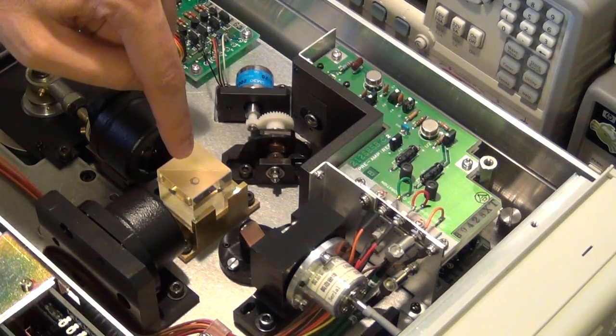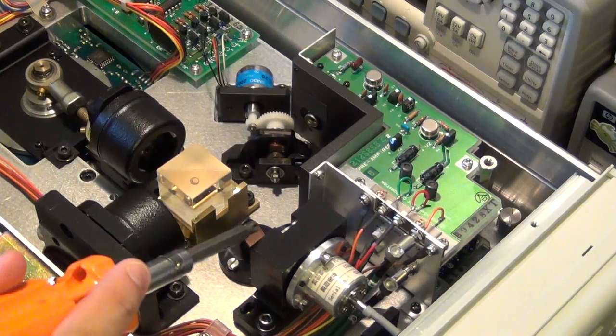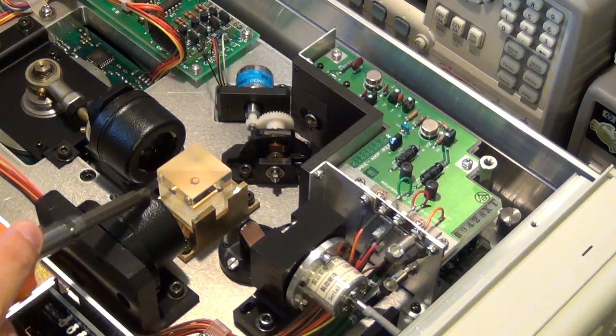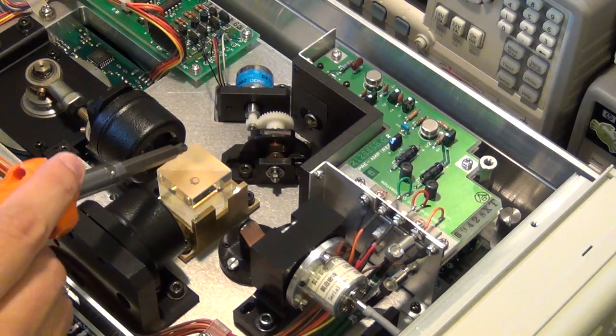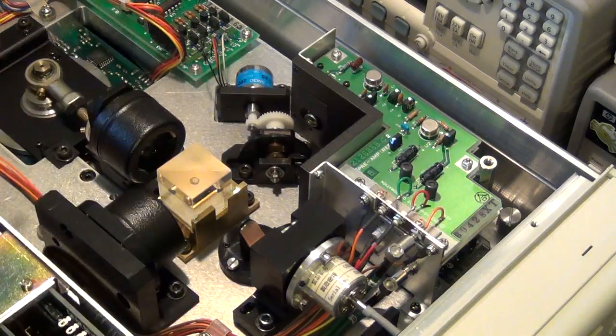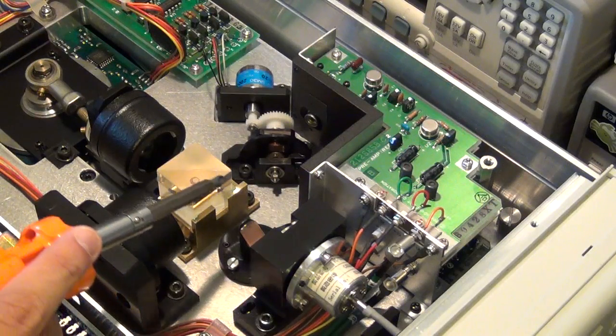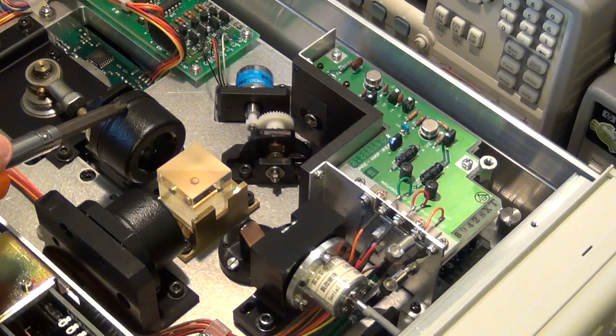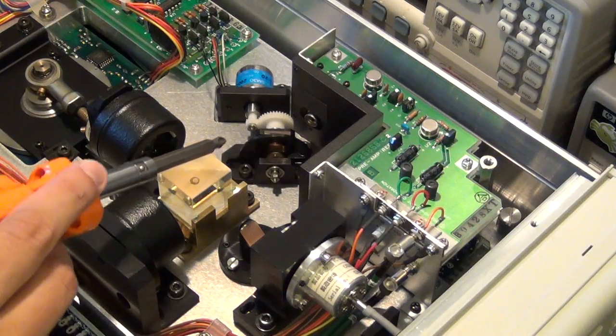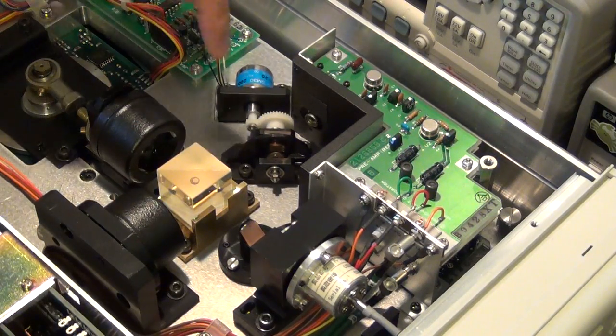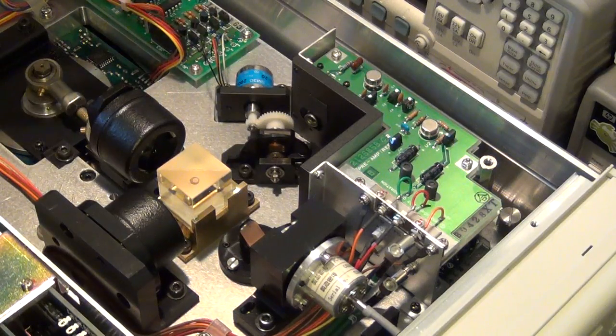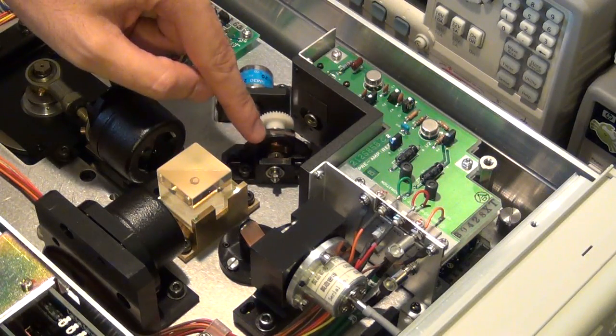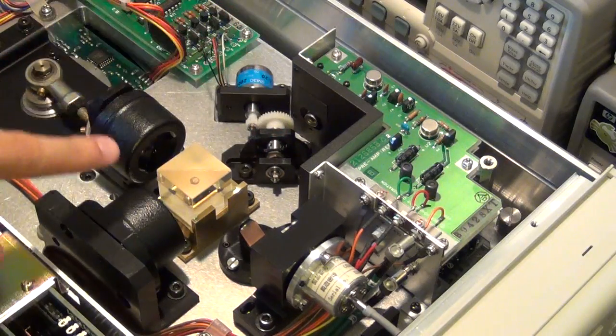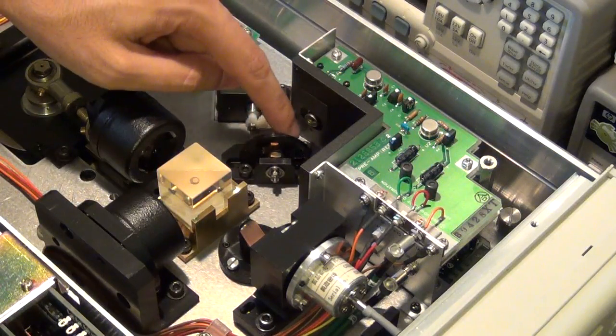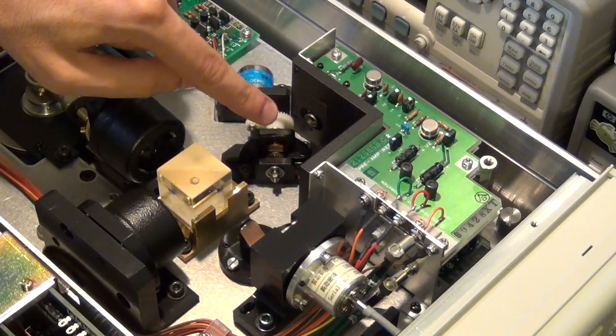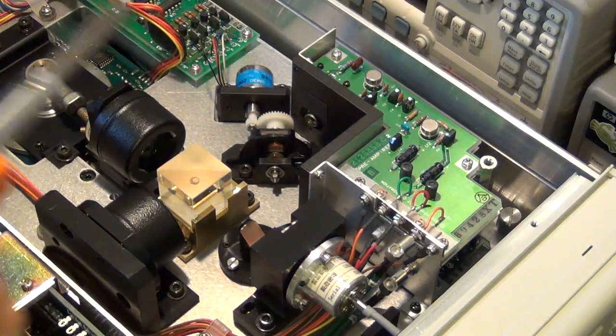Instead of a mirror, it uses two prisms that are back to back. So this light goes through this prism, bounces against this mirror, goes back through the prism, and shines on the sensor, which is all the way over there. The other path, the light goes through the prism, bounces against this mirror, comes back through the prism, and goes back again to the sensor. So because this thing can measure such a wide range of wavelengths, there's actually a mirror in here. So this guy can rotate. It can either stay in this way, where the light goes right through, or it can be in this position, where there is a mirror, and the light will bounce against the mirror and go to a different detector. So there's actually multiple detectors.